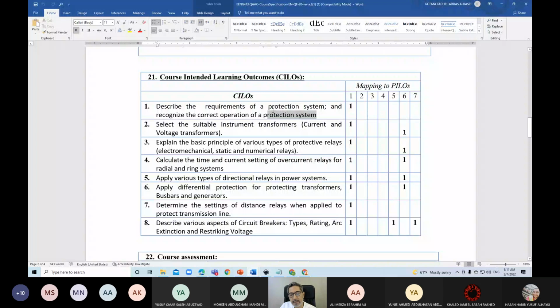Then in the next chapter, we'll focus on instrument transformers, and you have two types of instrument transformers, current and voltage transformers. These are not the same as the power transformer that you have taken in the machines course. It is a transformer dedicated for measurements and protection. So you will know how to select properly a current transformer for the protection or measurement applications, such that this transformer will not get saturated during short circuits.